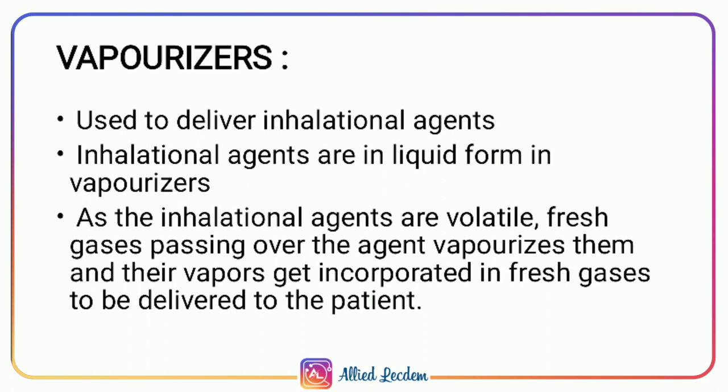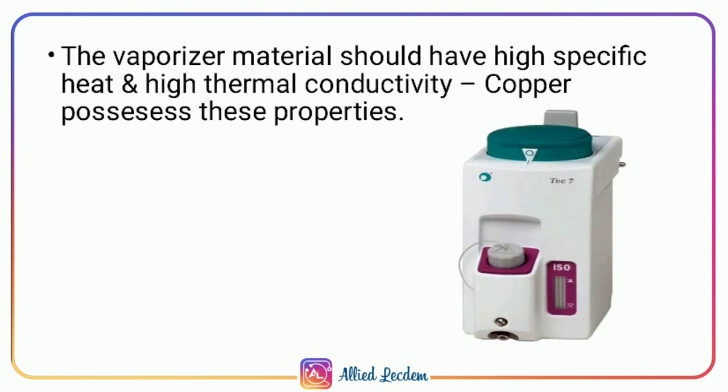Vaporizers are used to deliver inhalational agents. The inhalational agents are in liquid form inside vaporizers. As these agents are volatile — easily evaporated at normal temperature — fresh gases passing over the agent vaporize them, and the vapor gets incorporated into the fresh gas delivered to the patient. The vaporizer material should have high specific heat and high thermal conductivity; copper possesses these properties.